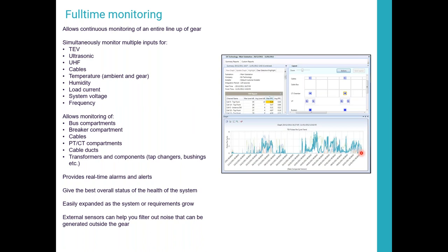So it definitely has some benefits on high profile circuits over doing spot monitoring or spot checking. There's more cost associated with it, so a lot of times putting it on every circuit you have may not be better. You may not see a benefit to that, but if in your facility you have circuits that are definitely critical to you and that truly keep you up at night, you then may want to consider either very frequent spot checking with the handheld instruments or going to a full-time monitoring system.